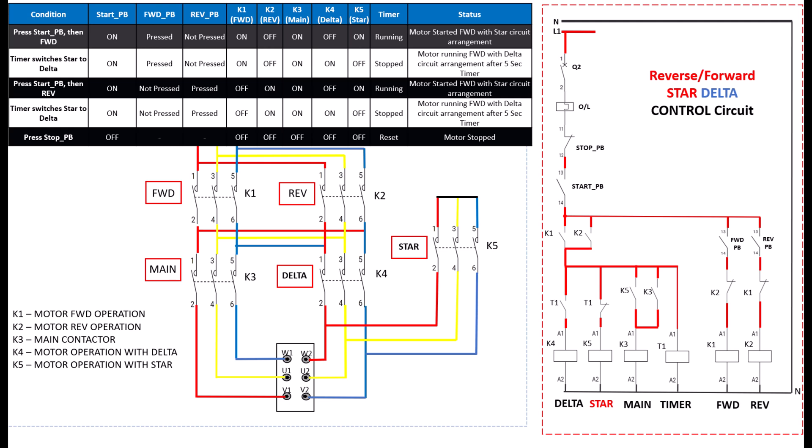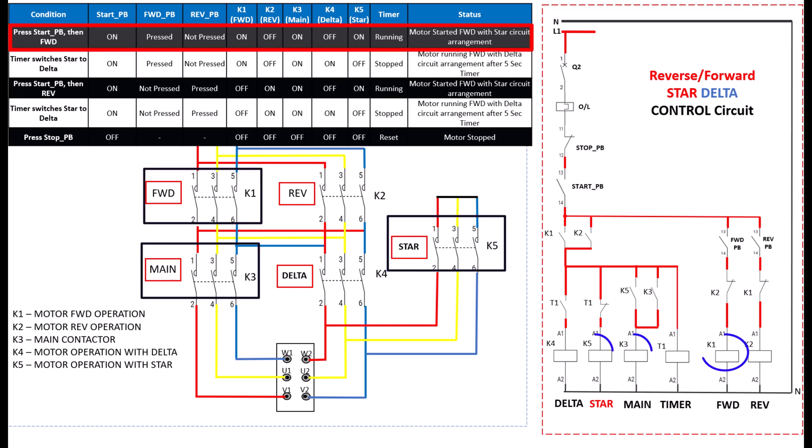Case one. You need to run the motor in forward direction with star configuration and then delta configuration. When you press the start push button, followed by the forward push button, what happens? K1 forward contactor, K3 main contactor, and K5 star contactor engage. The motor starts running in the forward direction using the star configuration. After five seconds, the timer deactivates K5 star contactor and energizes K4 delta contactor through the interlock. Now, the motor continues to run in the forward direction in full delta mode.